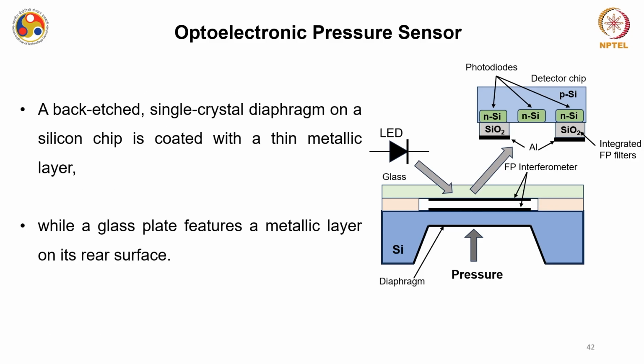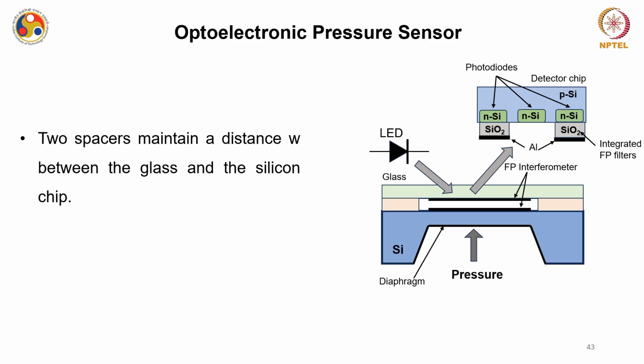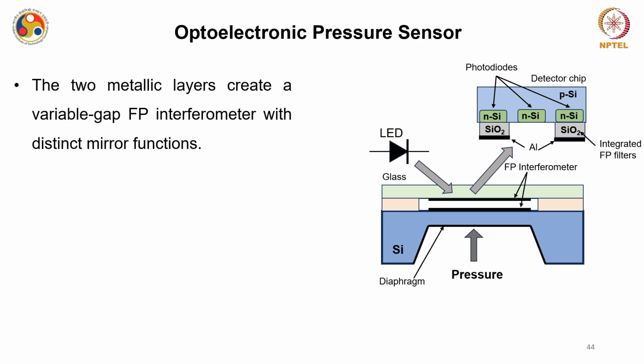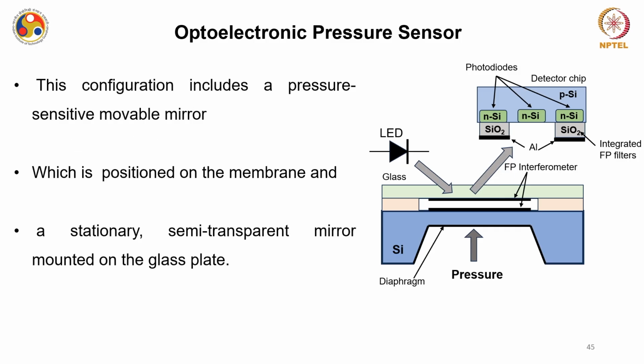Okay, so a back-etched single crystal diaphragm on a silicon chip is coated with a thin metallic layer, while a glass plate features a metallic layer on its rear surface. I am talking about that. Two spacers maintain a distance W between the glass and the silicon chip. The two metallic layers create a variable gap Fabry-Perot interferometer with distinct mirror function.